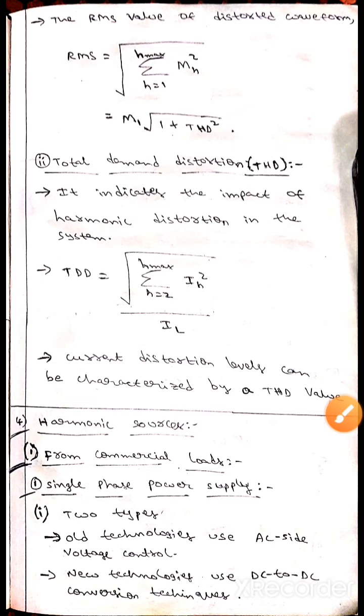The formula for TDD is TDD equals root over sigma h equals two to h max, Ih square by IL. Current distortion levels can be characterized by a TDD value.